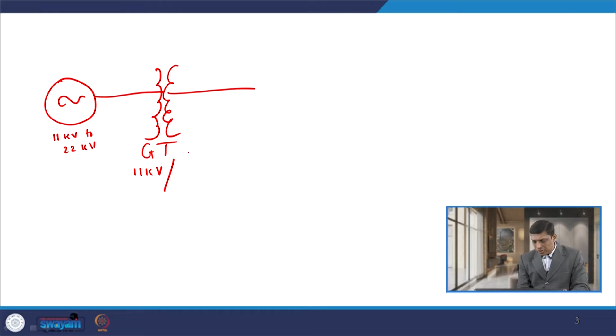The generating transformer is nothing but the transformer which steps up the voltage from, let us say, 11 kV to at the most, let us say, 400 kV. So, the voltage is stepped up from 11 kV to 400 kV, and then from the switchyard of the power station, this 400 kV high voltage is transferred. Power is transferred at high voltages because as the value of voltage increases, the magnitude of current reduces. So, we can achieve economy as far as the cross sectional area of conductor is concerned.